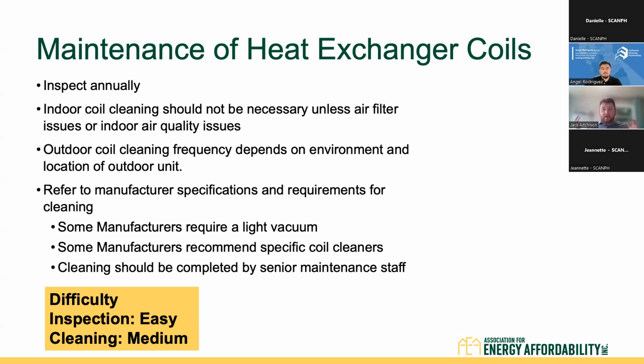Ultimately, these outdoor coils are subject to the outside. They do not have a filter with them. So you really need to make sure that you're inspecting these outdoor coils, because they're subject to outside elements and they don't have a filter. When we're thinking about maintaining coils, you really should be thinking about the outdoor coil. And if you're doing your air filter replacements and inspections, you should not be worried about your indoor coil.